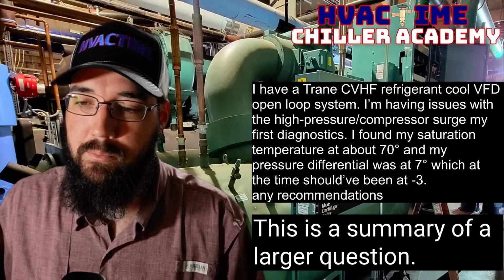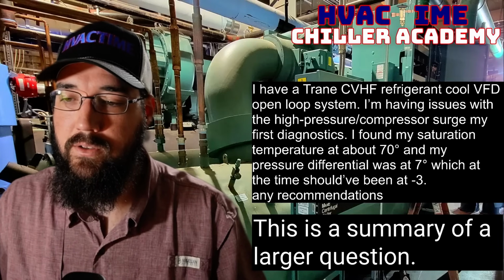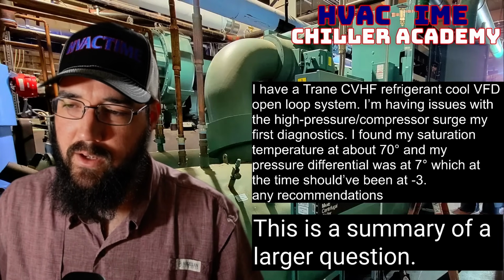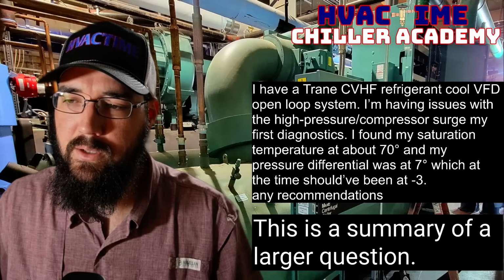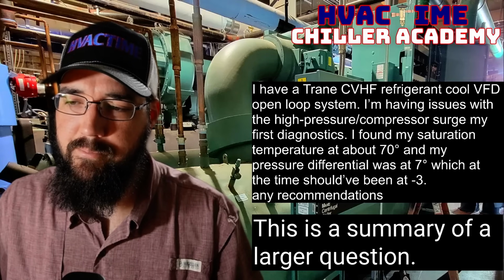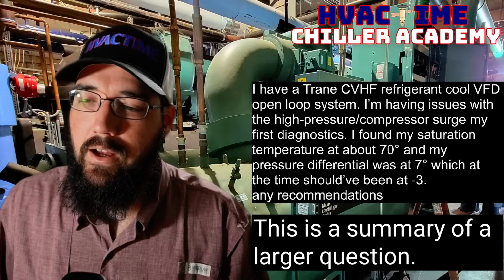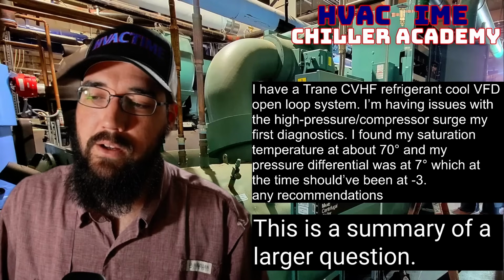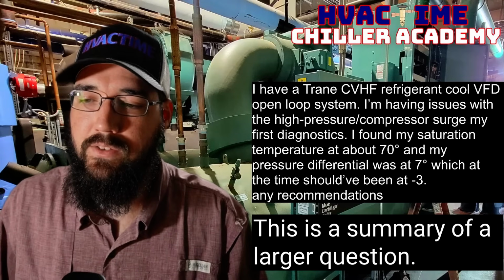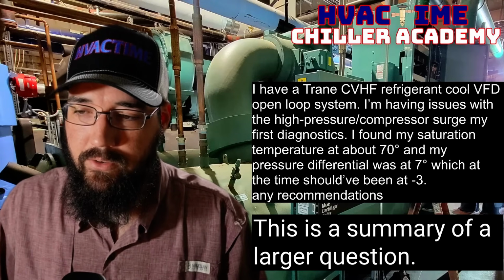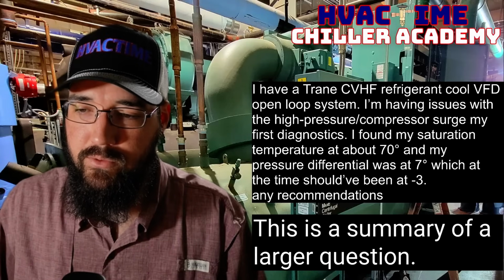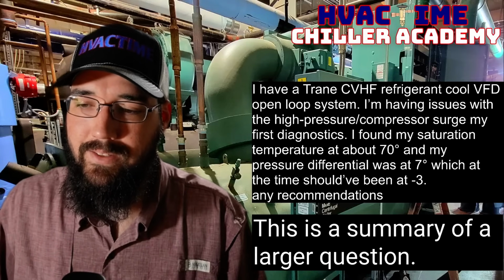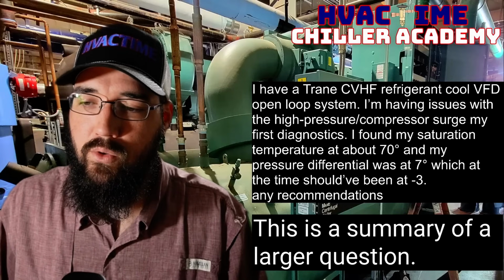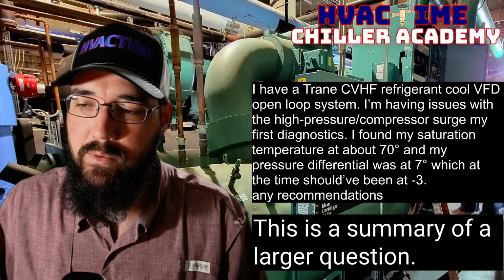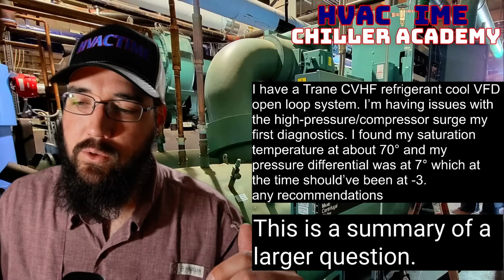Okay, so you put the pumps back in hand and you force the flow up. That's interesting. Okay. I also ran the system for about 20 minutes, and I found my saturation temperature at 70 degrees and my pressure differential was at 7 degrees, which at the time should have been at -3, right?